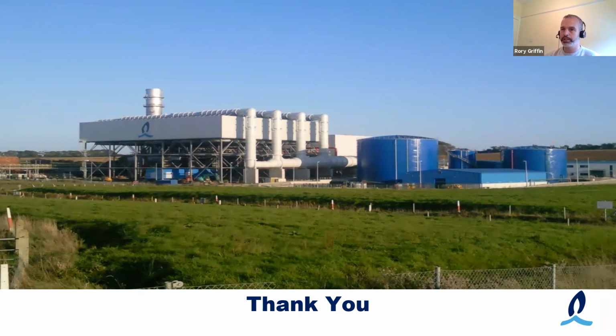But it would be at the instruction of the control room and EirGrid and SONI, and they'd have to decide the nature of the blackout and whether it is safe to bring in 80 megawatts quickly, because the risk is if you bring it in too quickly, you could collapse the whole thing again and you're back to square one.